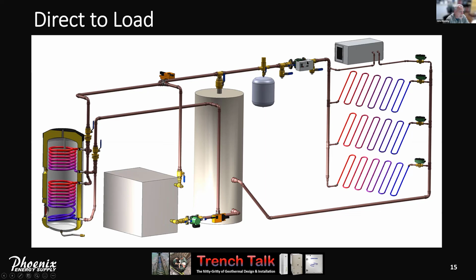You can do the same strategy with zone pumps, but you may get phantom flow through some of the circuits, even with a zone pump. If you're going to put a zone pump in, you could put a check valve in. That would minimize phantom flow, but it may not eliminate it.